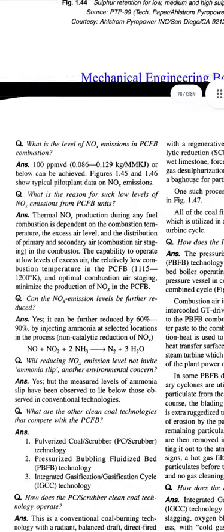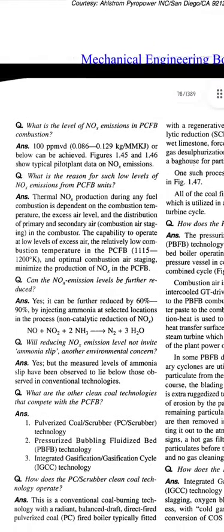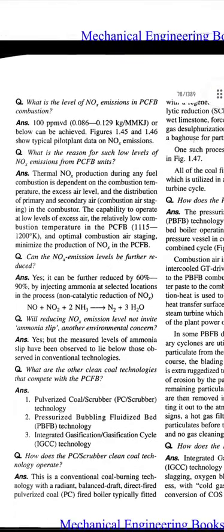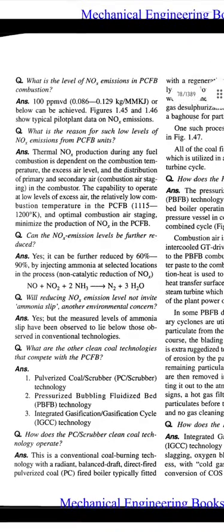Next question: What is the level of NOx emissions in PCFB combustion? Answer: 100 ppm (0.086 to 0.129 kg/GJ) or below can be achieved. The figure shows typical pilot plant data on NOx emissions.